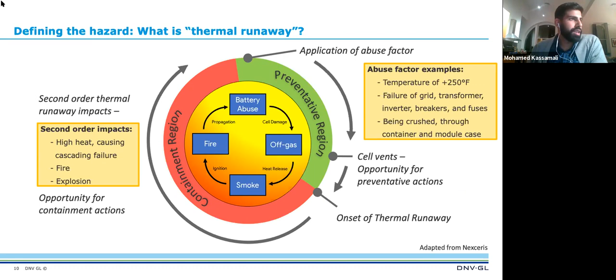In the case of thermal runaway, do we have protections in place? In the case of fire, do we have protections such as clean agent suppression, water suppression, et cetera? We want to build more barriers into these threat and consequence pathways to create layers of protection within the system to prevent a larger, more catastrophic event.